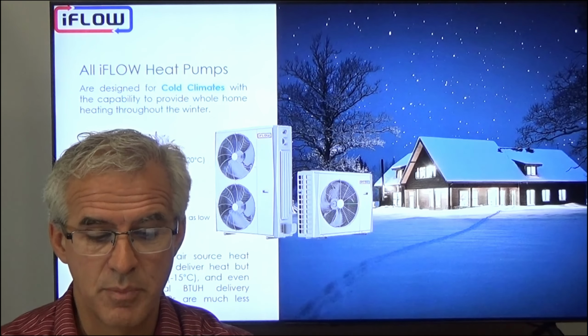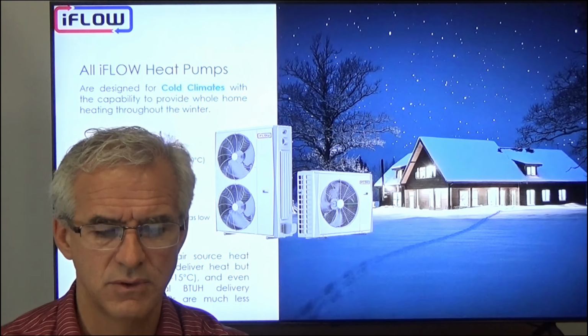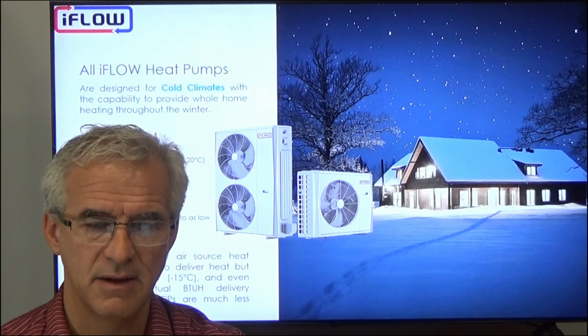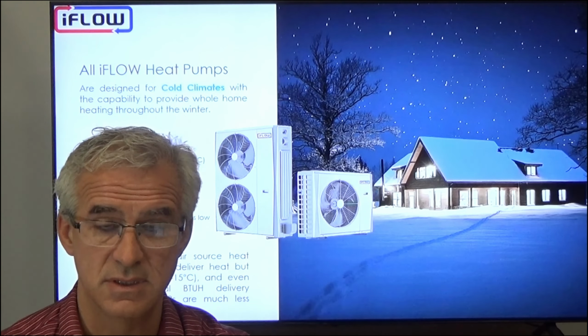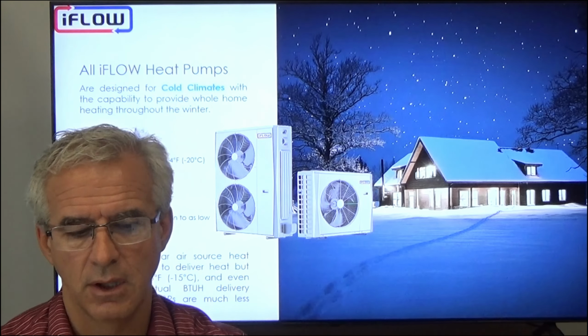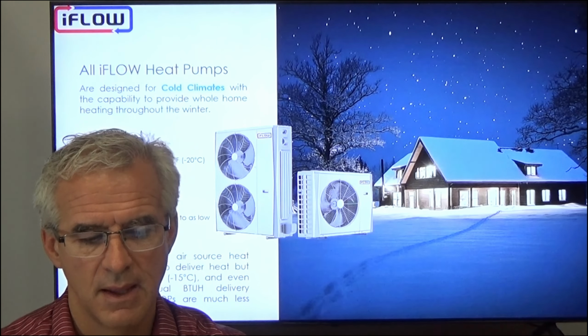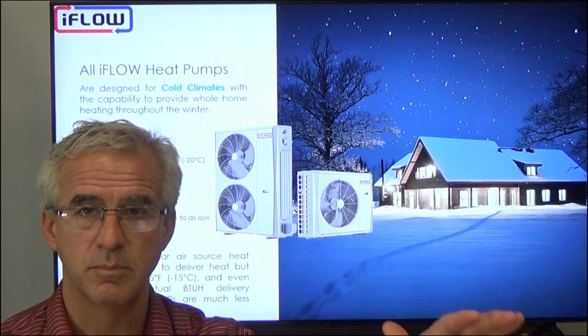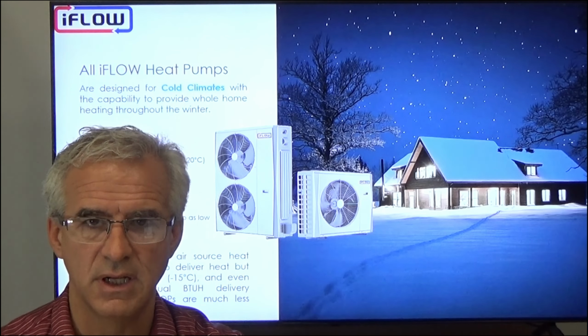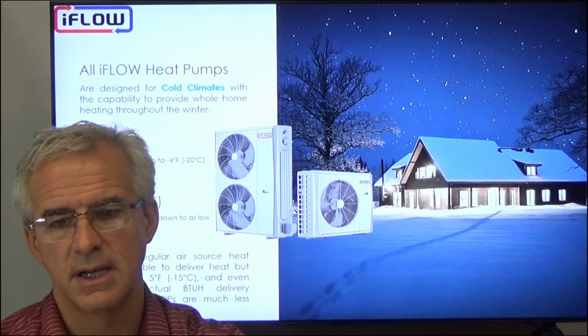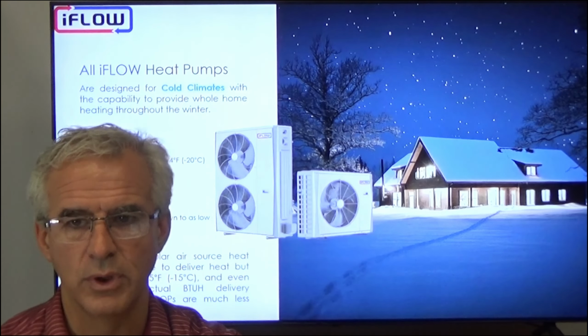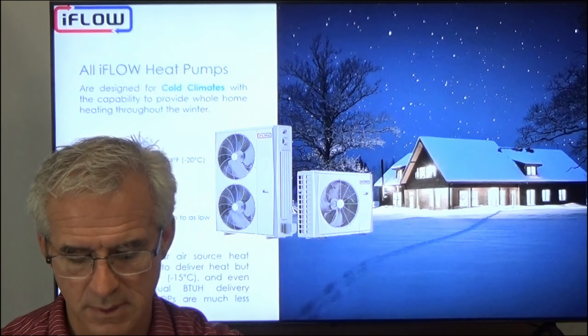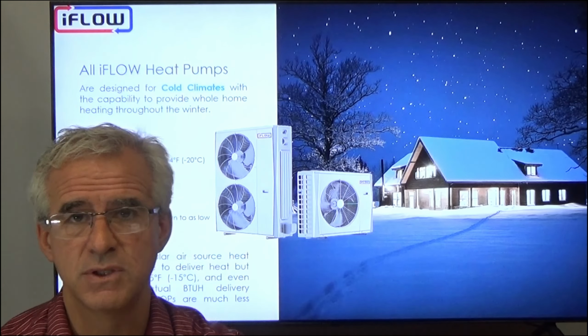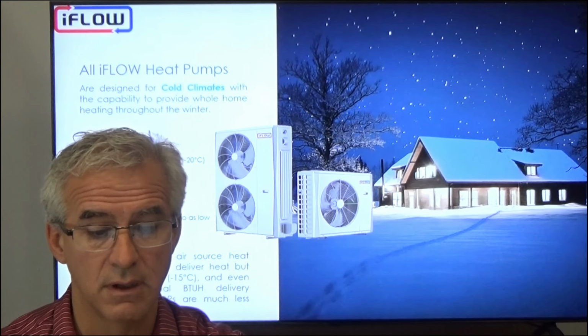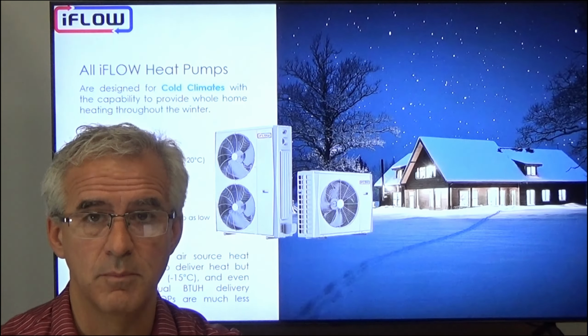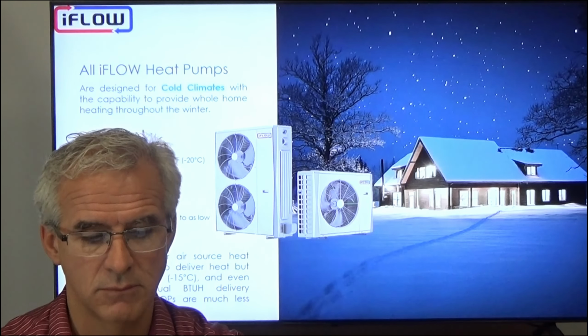Regular air source heat pumps are typically able to deliver down to minus 10, minus 15 Celsius, which is, let's say, 5 Fahrenheit. But even then, the actual delivery has dropped off significantly, and the COPs are usually significantly less, down around 1.4 or 1.5 perhaps. So the cold climate heat pumps do have a significant advantage over their non-cold climate heat pump alternatives.